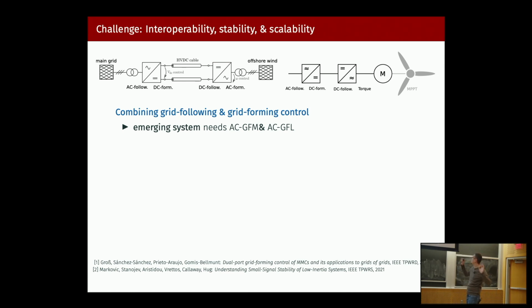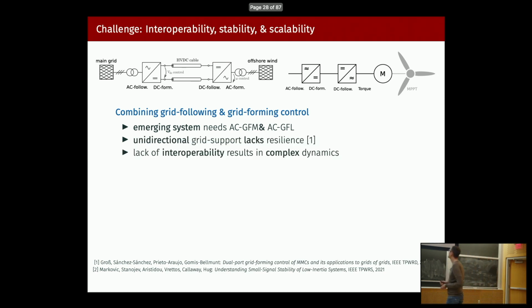If you stick to the paradigm of AC grid-forming and AC grid-following control as your only two choices to operate a power system as it is today, you need a mix of both. The problem is, look at an HVDC system connecting two AC systems—one converter needs to stabilize the DC voltage. Look at the wind turbine, a so-called type 4 wind turbine that rectifies AC into DC, then has another converter to rectify the AC that comes from the wind turbine machine. To manage any of these, you need to stabilize the DC voltage at some point, so you need a mix of AC grid-forming and AC grid-following control.